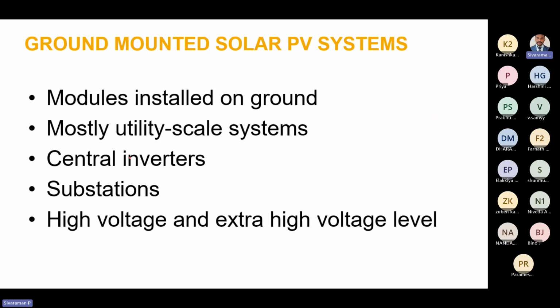In this system, mostly we will use central inverters. Earlier I explained the different types of inverters available for solar PV applications. As a recall, I will reiterate: string inverter, central inverter, and micro inverter. Most ground mounted PV applications widely use central inverters, and there will be a substation. I have not explained anything about substations till now, because in rooftop based applications, substations will not be required or will not be in place.